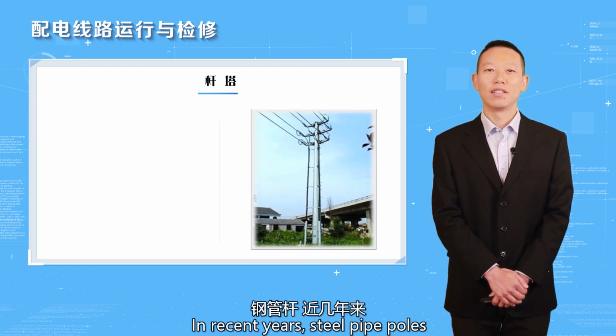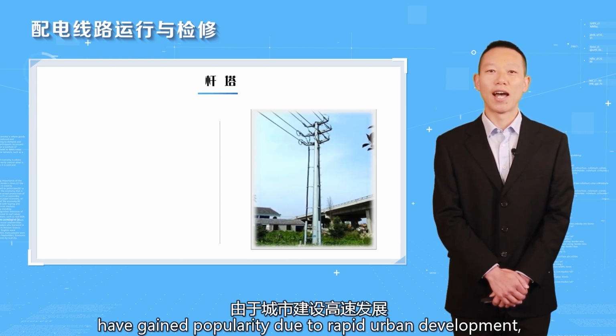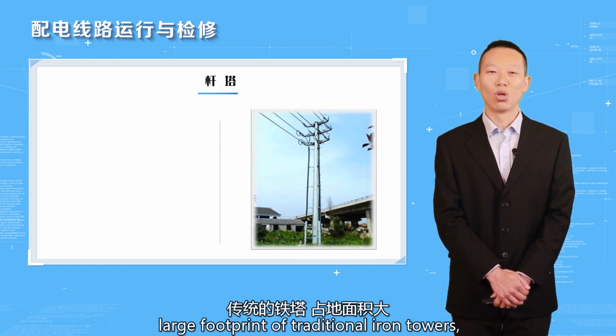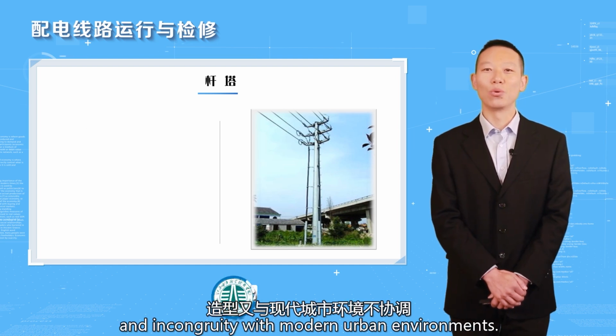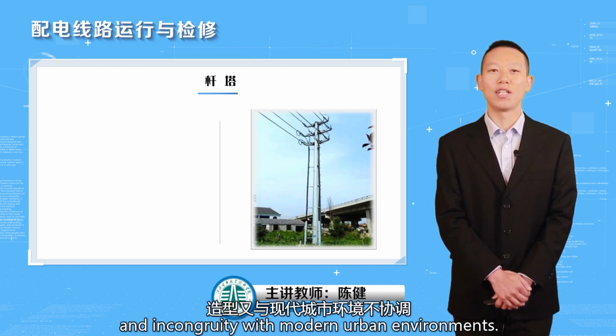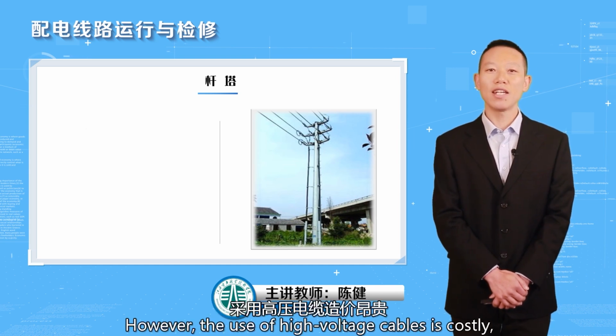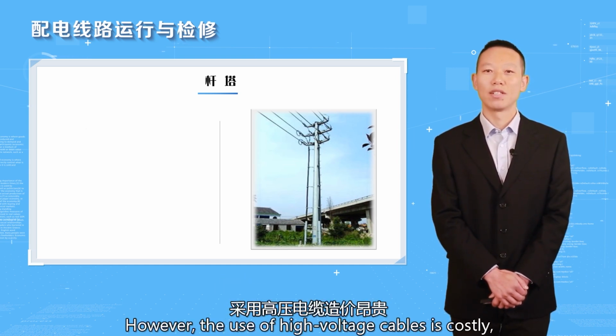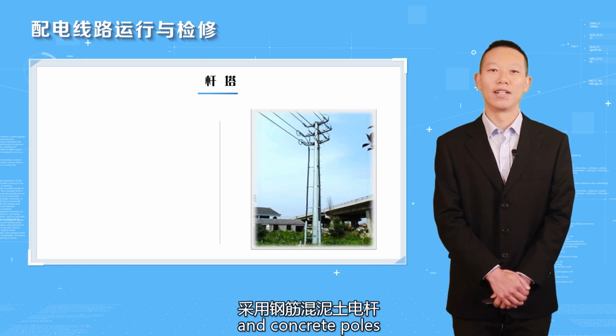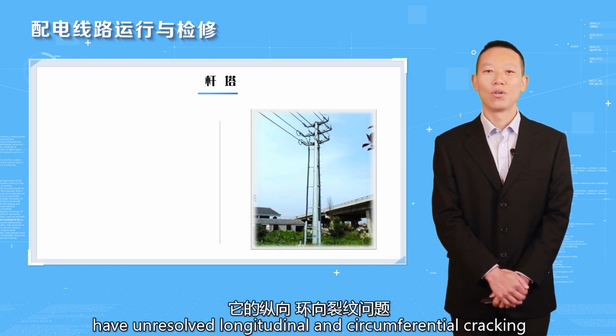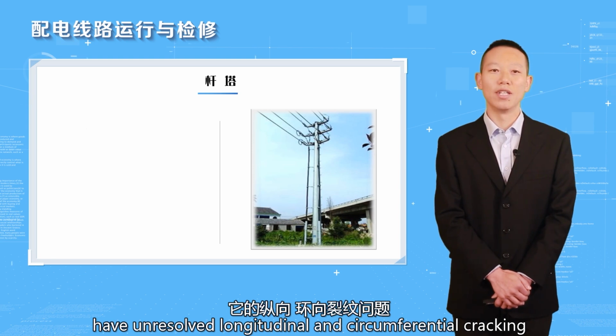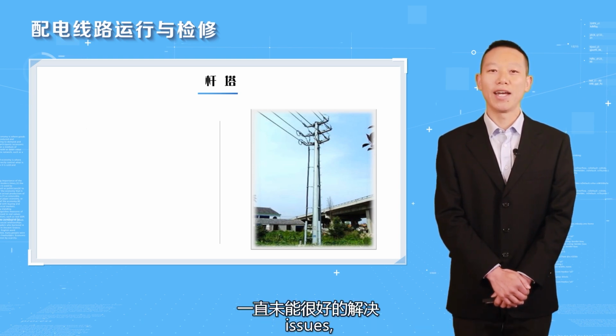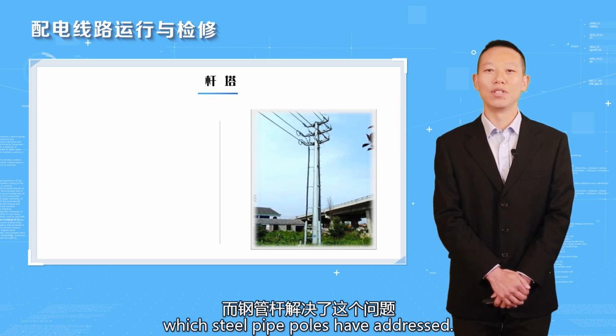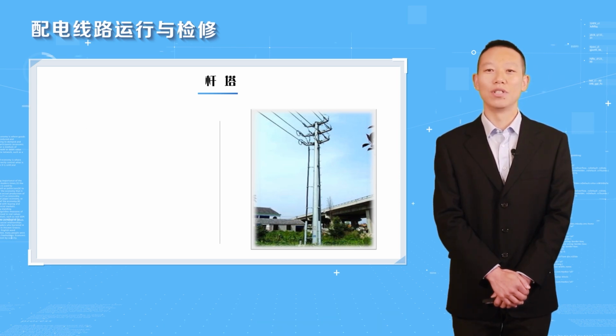In recent years, steel pipe poles have gained popularity due to rapid urban development, large footprint of traditional iron towers, and incongruity with modern urban environments. However, the use of high-voltage cable is costly, and concrete poles have unsolved longitudinal and circumferential cracking issues, which steel pipe poles have addressed.